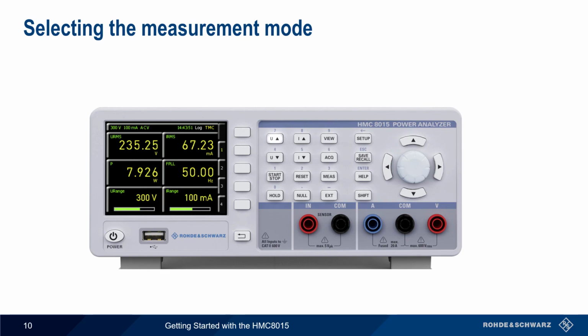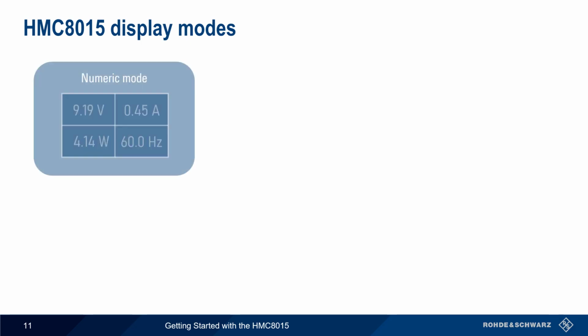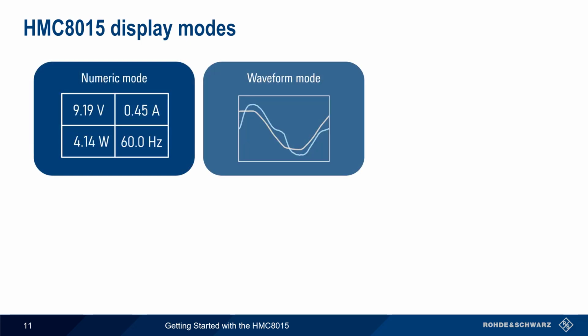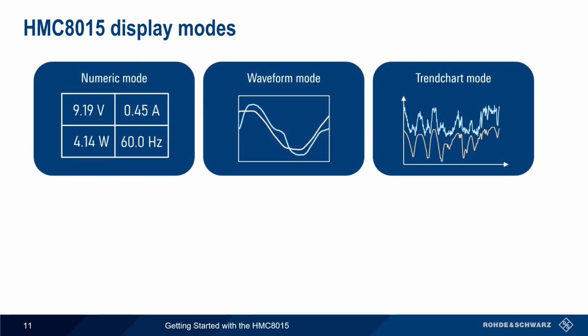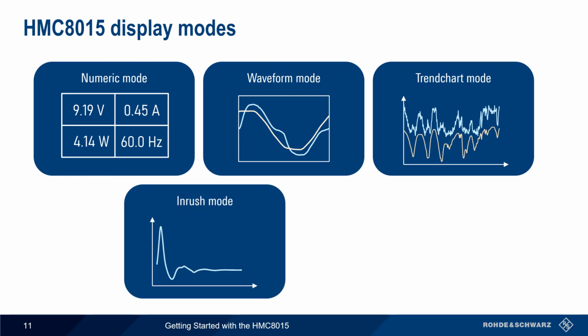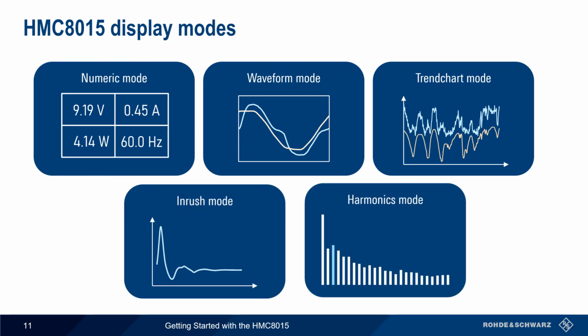The first step in making measurements with the HMC is selecting the measurement mode, which is selected using the View hard key. The 5 different measurement modes are Numeric mode, Waveform mode, Trendchart mode, Inrush mode, and Harmonics mode. Let's look at each of these modes in more detail and explain how they're configured and used, starting with Numeric mode.